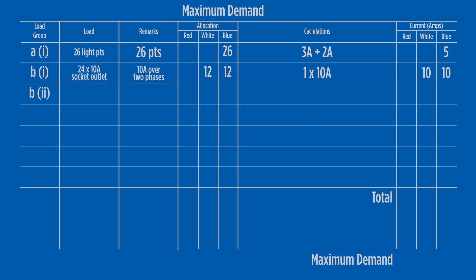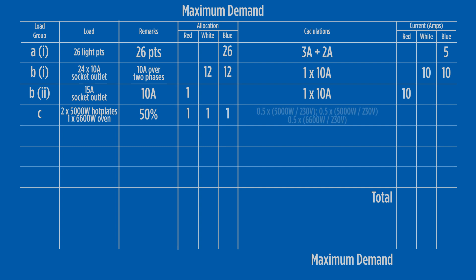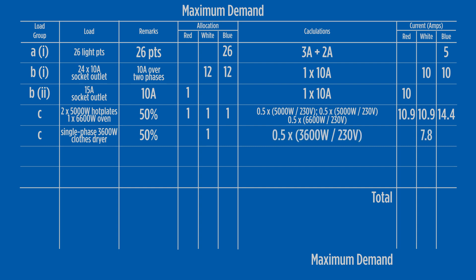In load group B2, we have one 15-amp single-phase outlet that contributes 10 amps to the red phase. The 16.6 kilowatt three-phase range contributes 5 kilowatts to two phases and 6.6 kilowatts to the third phase. Calculating current from load group C gives 10.9, 10.9 and 14.4 amps. The single-phase clothes dryer contributes 7.8 amps to the white phase from the calculation.